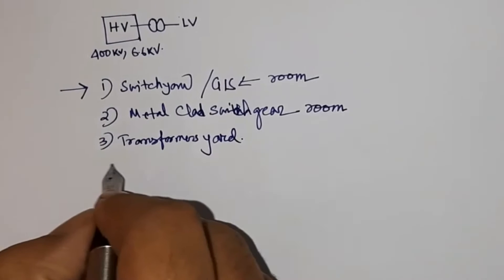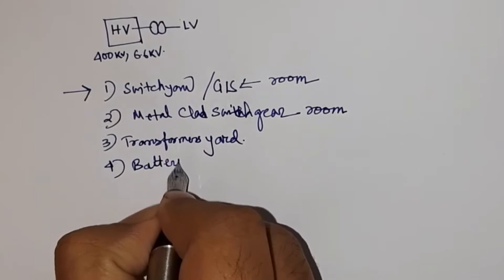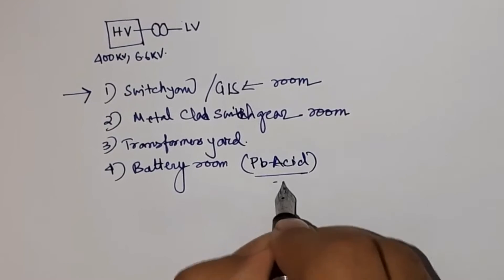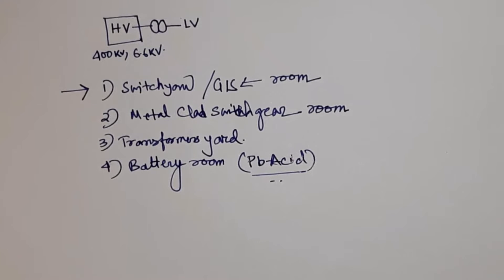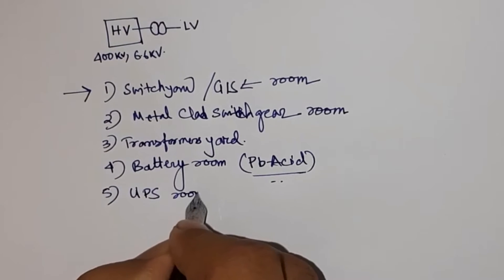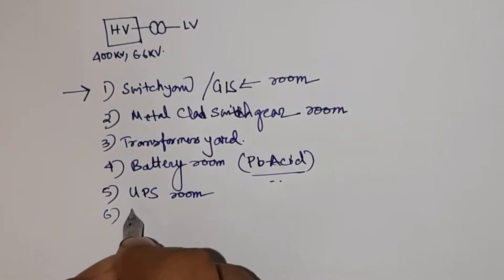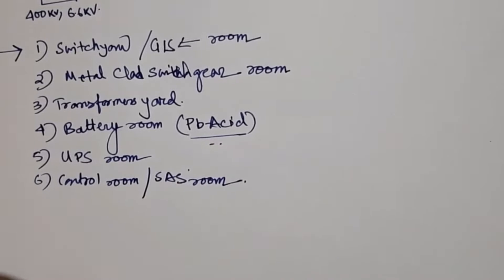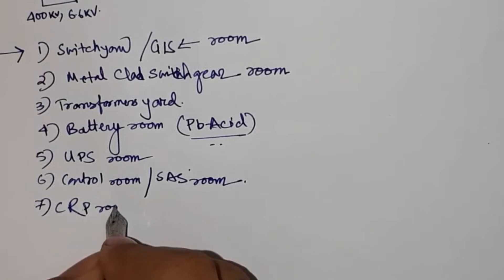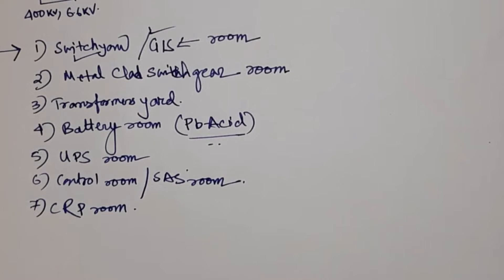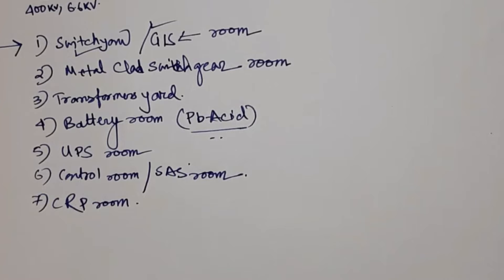Inside the substation building there shall be a battery room for housing batteries. This is mainly required for lead-acid batteries. If it is a valve-regulated lead-acid (VRLA) or sealed maintenance-free battery, then a separate battery room is not required. There shall also be a UPS room. Then there shall be a control room or substation automation system room, and a CRP (Control Relay Panel) room. The CRP room is required because relays cannot be installed outdoors in a switchyard, or inside a GIS, so a separate control relay panel must be installed.